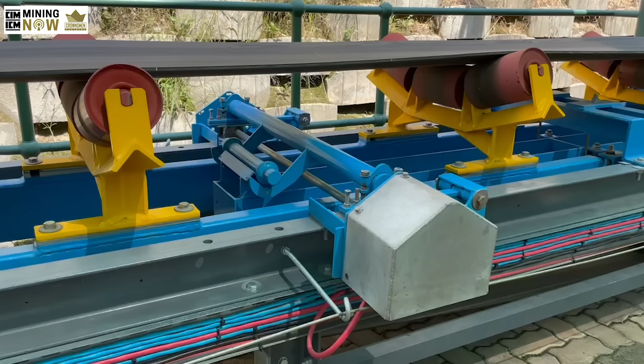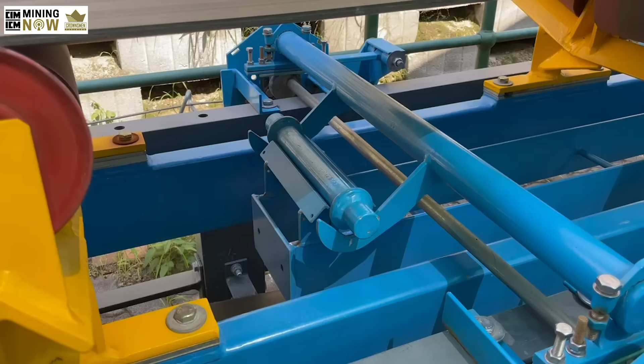On some of the installations, some plants at least, we've got over 100 installations. If you can imagine the amount of time available for maintenance relative to the number of machines they have, you'll see it's impossible - you cannot have one person. In fact, even if you had more than one person, you wouldn't have enough time in scheduled maintenance to go and calibrate every one of these instruments.